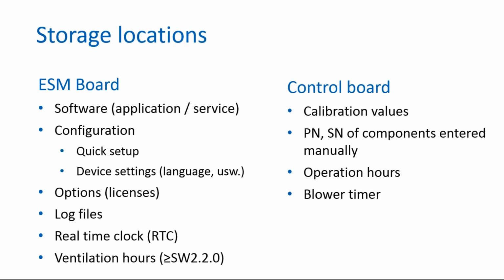The three capacitors located on the back of the board provide the power for the buzzer in case of a total power failure. It is useful to know where the device stores the various types of data, because both the ESM board and the control board have some storage capabilities. The ESM board contains the software for application and service, configuration parameters for application, such as quick setup and device settings, options, also called licenses, that provide various application functionalities, log files, the real-time clock, and in software version higher than or equal to version 2.2.0, it also contains the ventilation hours.